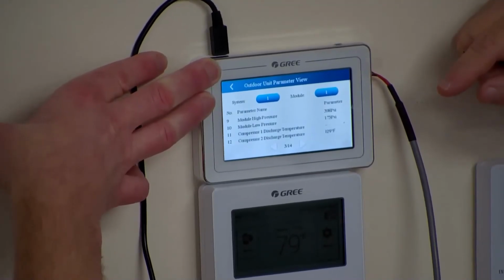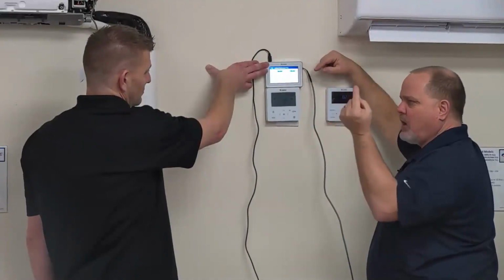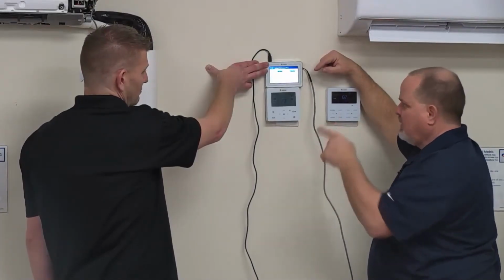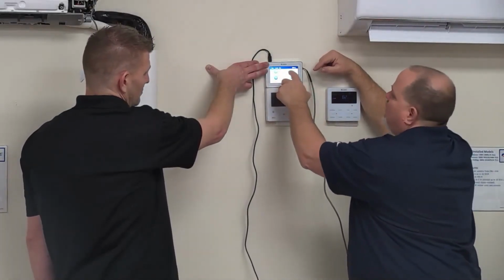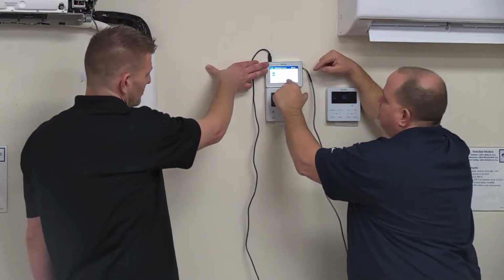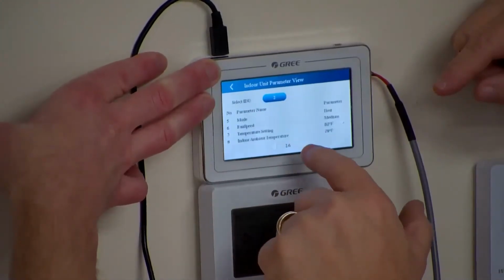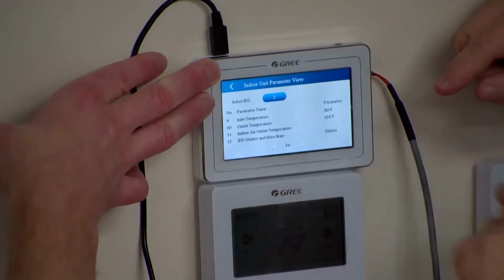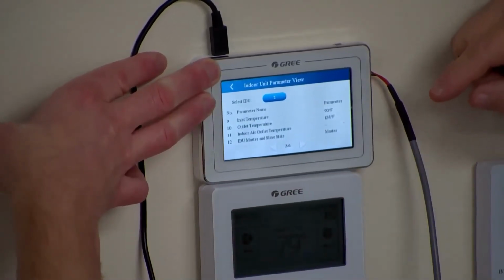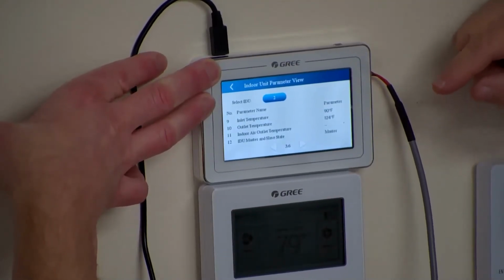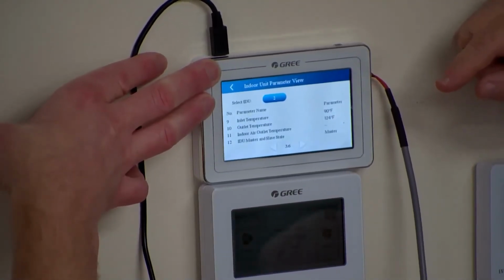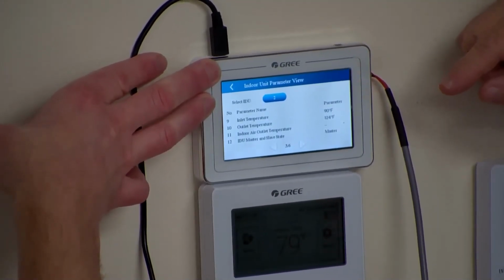So if I start shutting units down and all of a sudden my temperature rise goes up on that one, and my temperature split on my indoor unit, if I go back to indoor unit status, go to number 2, let's see what kind of differential. 90 degree inlet, 124 degree outlet. That's a 25 degree, or no, 35 degree, right? Yeah, 34. My math's horrible. 35 degree rise, differential across that. We're heating. We're absolutely heating. That's what I want to see.